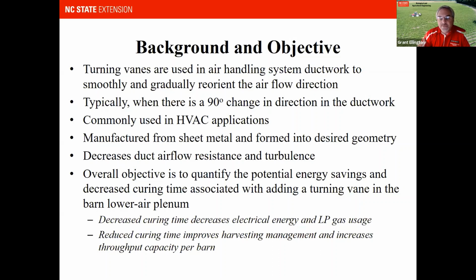So turning vanes, and you'll see some pictures of this as we move along, are manufactured from sheet metal and then formed in some desired geometry. Typically it's rolled into some radius dimension. And once again, the desired effect is that the turning vane is used to decrease the duct airflow resistance and turbulence, therefore making more air available and making the airflow more uniform across that ductwork, in this case, the lower air plenum in a bulk barn.